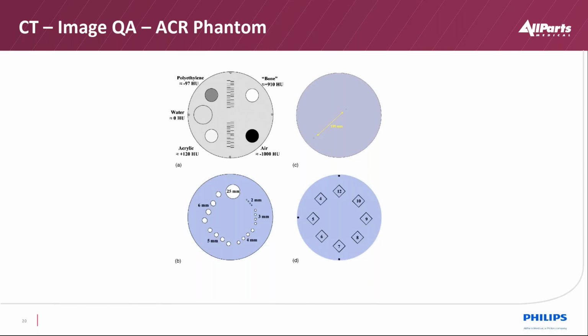We have the ranges of CT numbers. You can tell polyethylene and acrylic gives us the high and low ranges of soft tissue of about plus or minus 100. The phantom will have a little bit wider aspect to that. Water will be in the center of that scaling. And then we also have to be able to determine distances. Sometimes biopsies are done with patients from CT scanners and also radiation therapy planning. So we actually have a couple of BBs that we can measure 100 millimeters to see if the scaling is actually right.